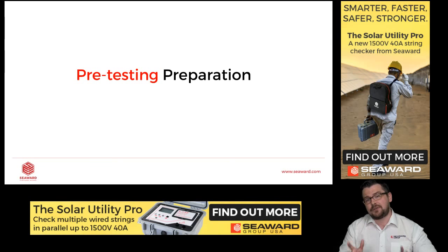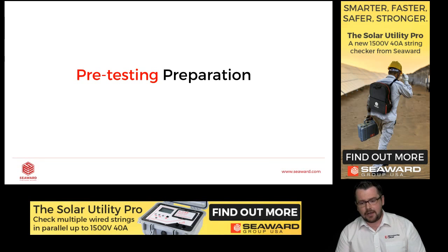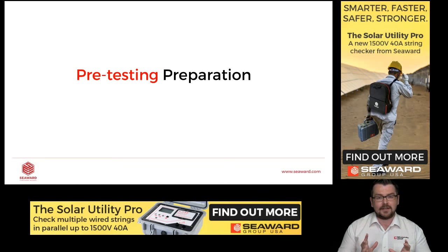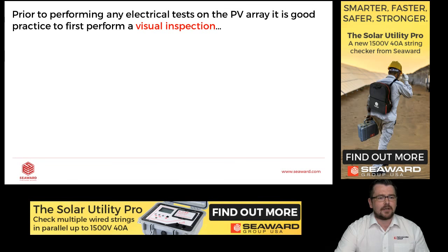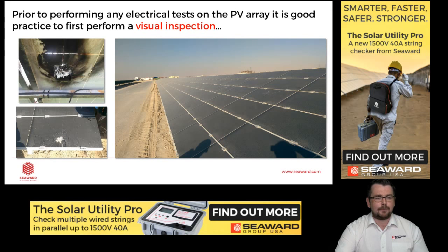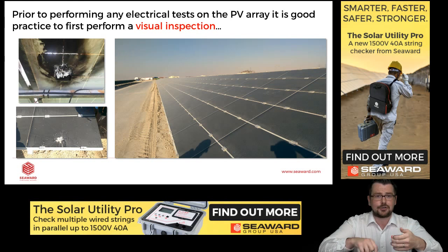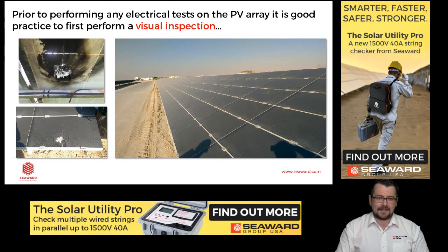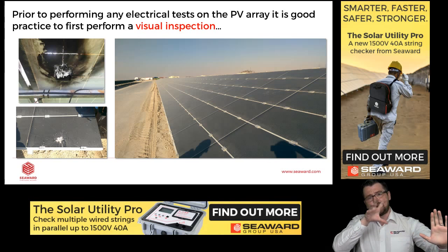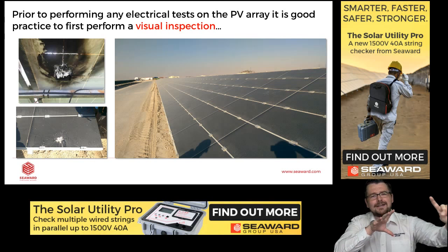So those were the differences between 1000 volt and 1500 volt systems. And what I like to say to our users is, before you even connect your instrument, let's do some pre-testing preparation. So the very first thing we should do is the visual inspection. This may sound like a bit of a given, but if you're going to test, we should take a look at what we're testing first. And you would be surprised how many people straight away disconnect panels, connect the instrument, test, without even looking at what they're testing. So particularly if you're working at the combiner box, you could be testing a string that's 200 feet or even more down at the bottom of the table.